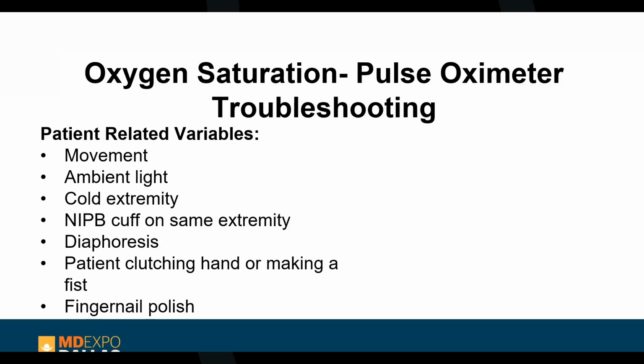Pulse oximeter troubleshooting. There's a lot of different variables to this one too. Movement is probably the biggest one. I don't care even if you have a Masimo pulse oximeter, it still gets some noise artifact in there, and that artifact can lead to an erroneous reading.